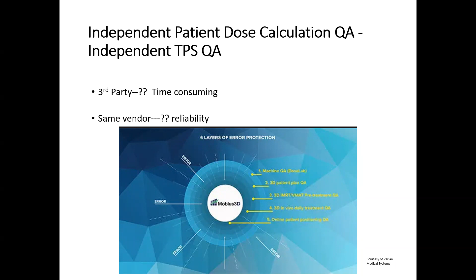So the known issues are always compatibility with multiple vendors. Some of the systems are user-friendly and some of them are not. Service and maintenance, and definitely the availability of parts if the machine is non-functional. Trained engineers: either you have a contractor or you have an on-site engineer. Equipment stability. In my experience, we had a machine from a vendor which worked very well with us with 99% uptime for 18 years. We had an upgraded and very advanced version of the machine from the same vendor, but the uptime of the machine was less than 95% in the first couple of months. So sometimes it is an equipment dependent thing.